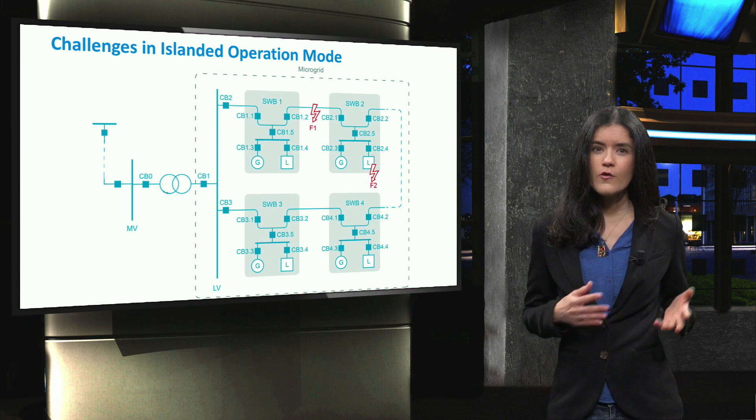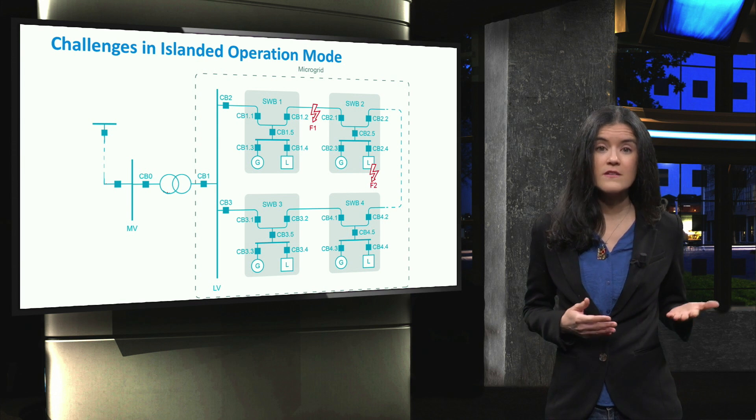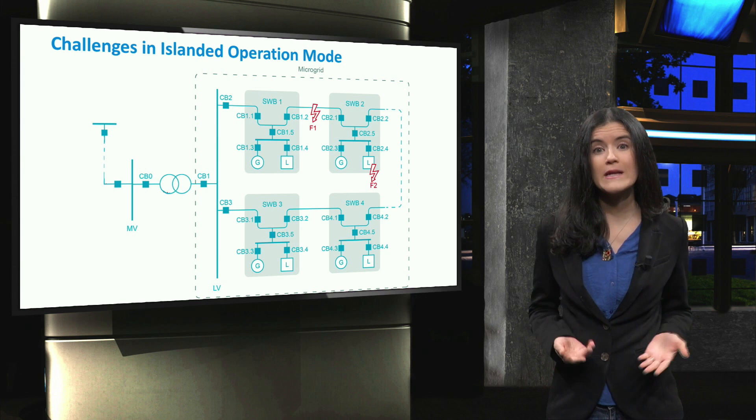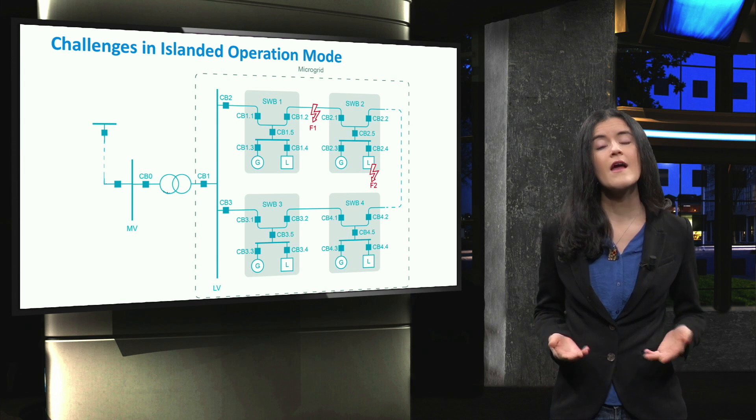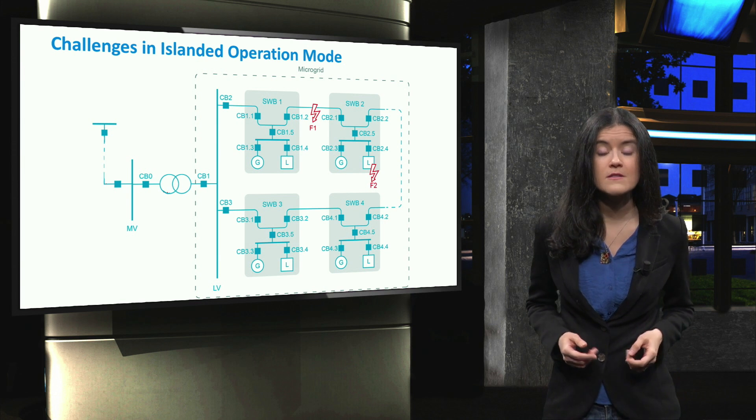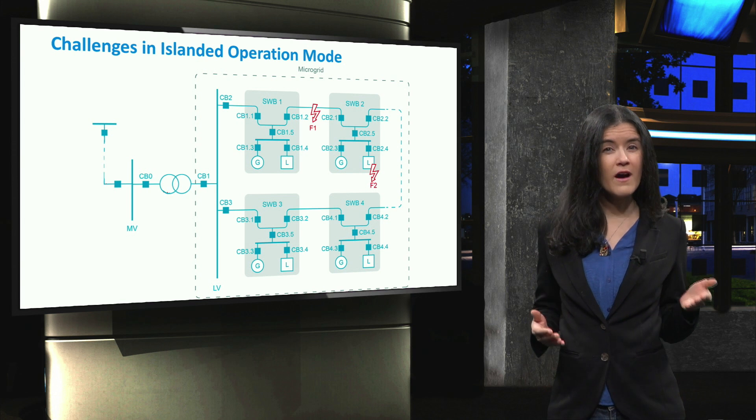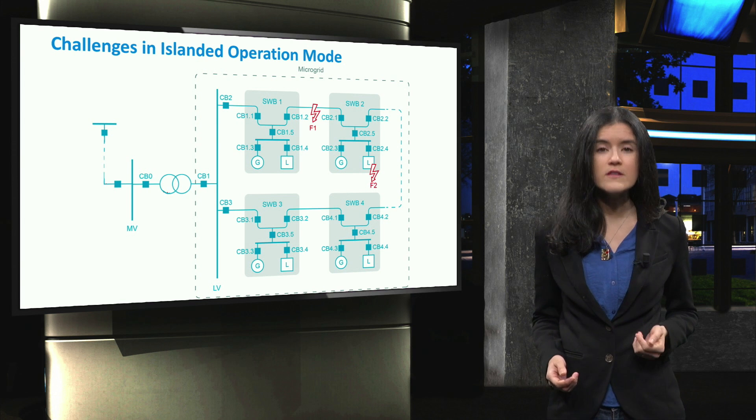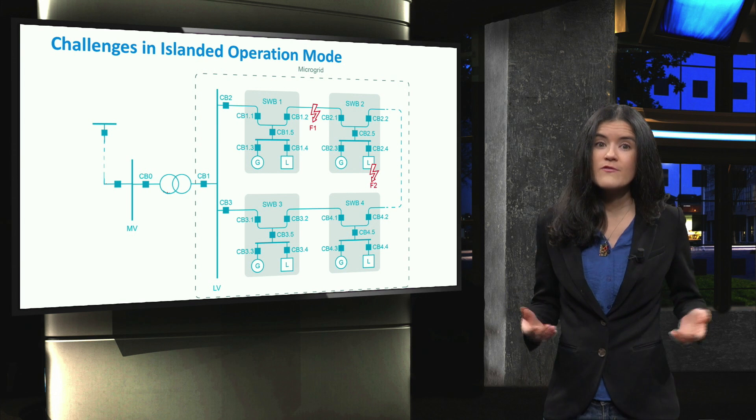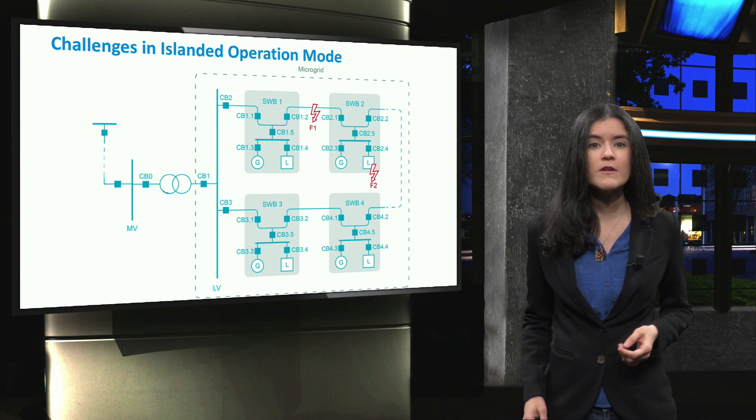Generally speaking, conventional electrical machines, such as asynchronous machines that are directly connected to the electrical network, are very sensitive to disturbances. Their fault current may reach five or six times the value of the nominal current. This makes fault current detection easy for the protection schemes.